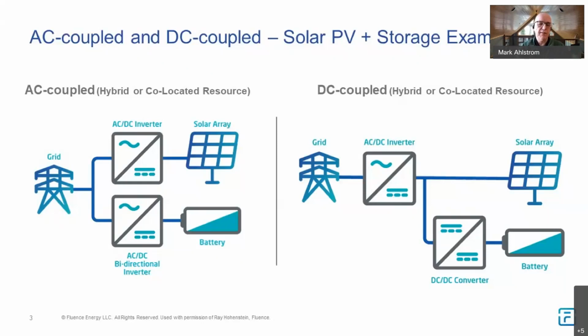Once I do that, say it's a 100 megawatt plant injecting into the grid, I could have 150 megawatts of solar generation at some instant. I'm using 100 to go out to the grid and 50 to charge the battery, so I'm still just injecting the maximum 100 megawatt injection limit. You could do it either way. It's purely an internal optimization.